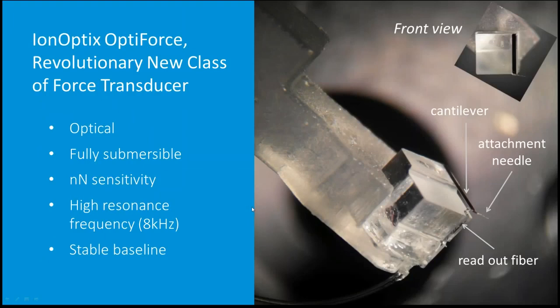The biggest problem with stable measurements is actually the air-water interface. So we wanted to have a force transducer that was fully submersible, and we ended up going for an optical transducer. What you see here is the block that forms the axial transducer with this cantilever. It's about 3 millimeters by 3 millimeters square.